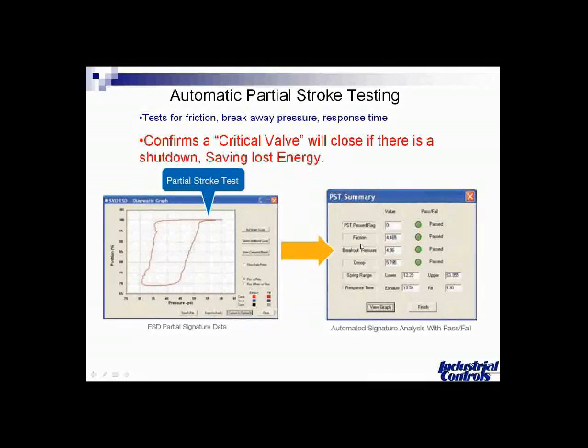And look at all the information that came back. It came back with how much friction there was, what the breakaway pressure was, what the response time was. I mean, this is amazing how much information you get about the health of your automated valves. And not only is this a safety situation, but you're going to be saving lost energy if these valves get stuck open and you can't get them shut. So there's multiple features here, and this technology is, I think, really fascinating and encouraging to see how smart the controllers have become now.